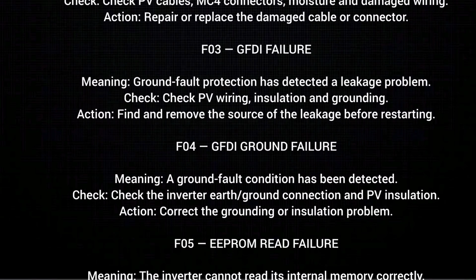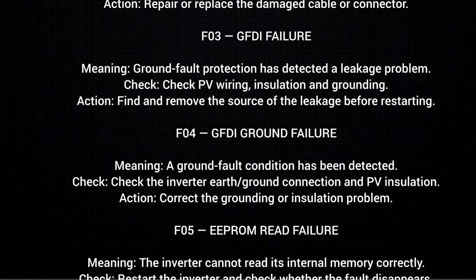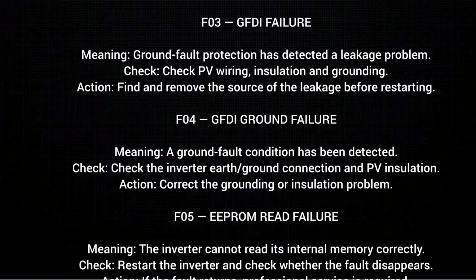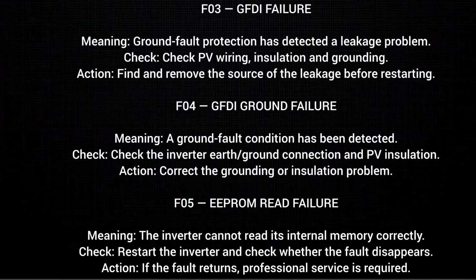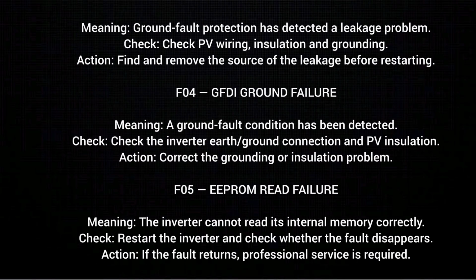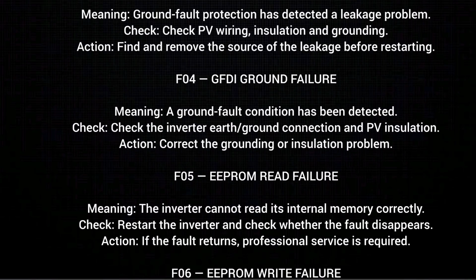F03 GFDI failure, meaning ground fault protection has detected a leakage problem. Check. Check PV wiring, insulation and grounding. Action. Find and remove the source of leakage before restarting.